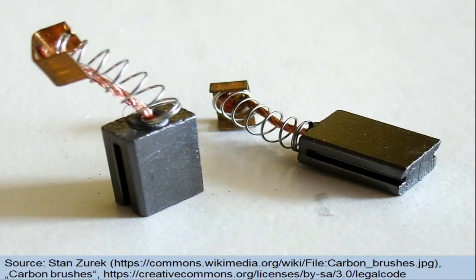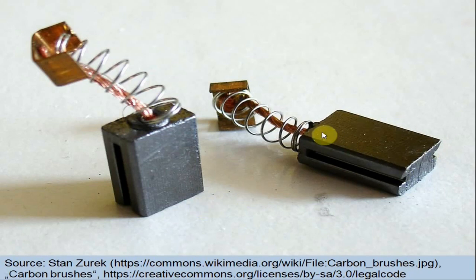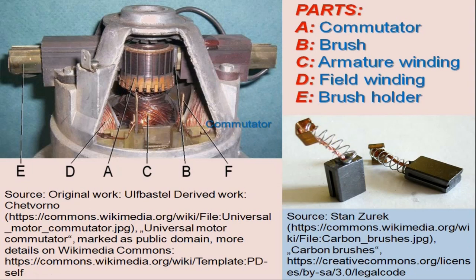The brushes are the means by which the current is collected from or conducted to the armature coils via commutator. The brushes are usually made of carbon or graphite and are in the shape of a rectangular bar. Each brush is supported by a metal holder known as a brush holder. A spring is usually used to adjust the pressure exerted on the commutator segments by each brush through its respective brush holder, in order to avoid excessive wear and to ensure proper electrical connection between the rotating commutator and the external circuit. An imperfect contact between the commutator and brushes due to inadequate pressure may certainly lead to sparking.